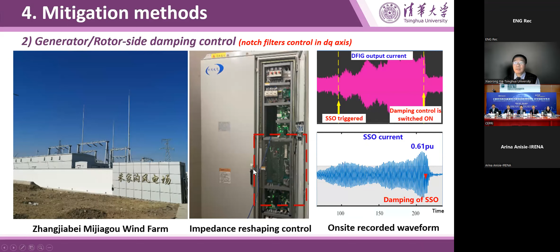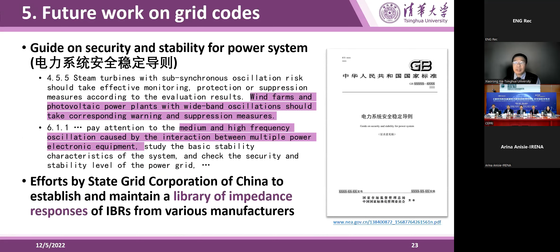At the end, I want to discuss further development on grid codes related to SSCI or other stability issues. In China, a recent grid standard, the Guide on the Security and Stability of Power System, covers oscillation stability issues. It is required that wind and PV power plants with wideband oscillation risk should take corresponding warning and suppression measures. There are also efforts established by the State Grid Corporation of China to establish and maintain a library of impedance responses of inverter-based resources from various manufacturers.